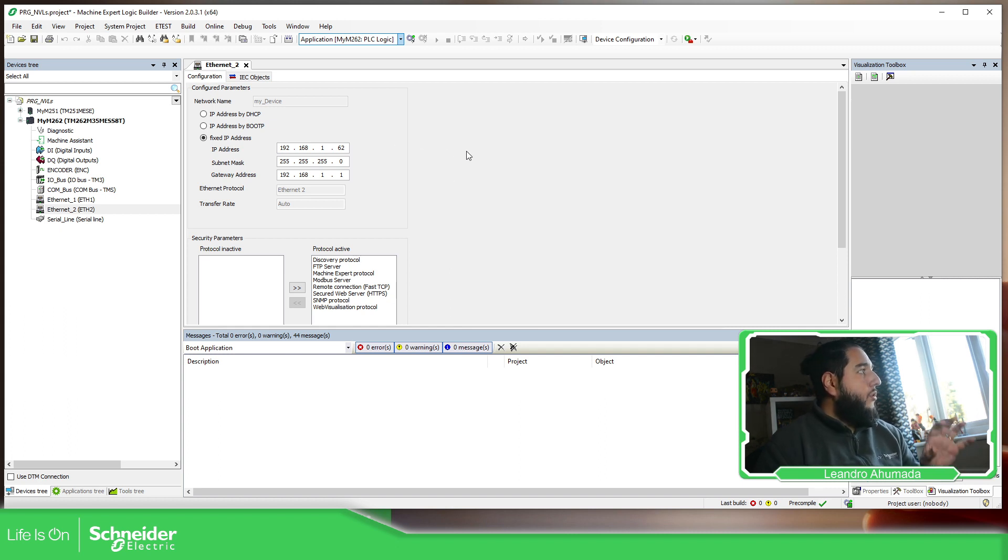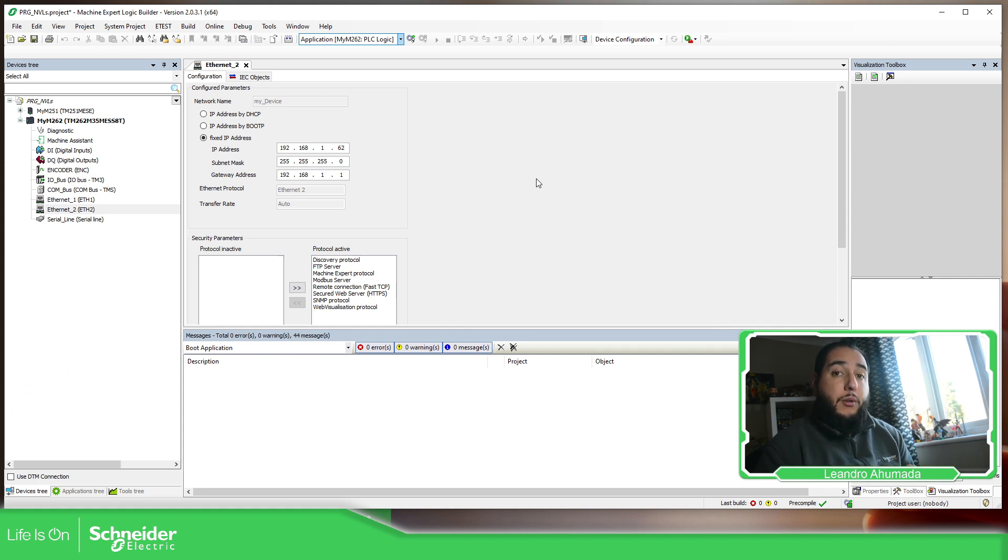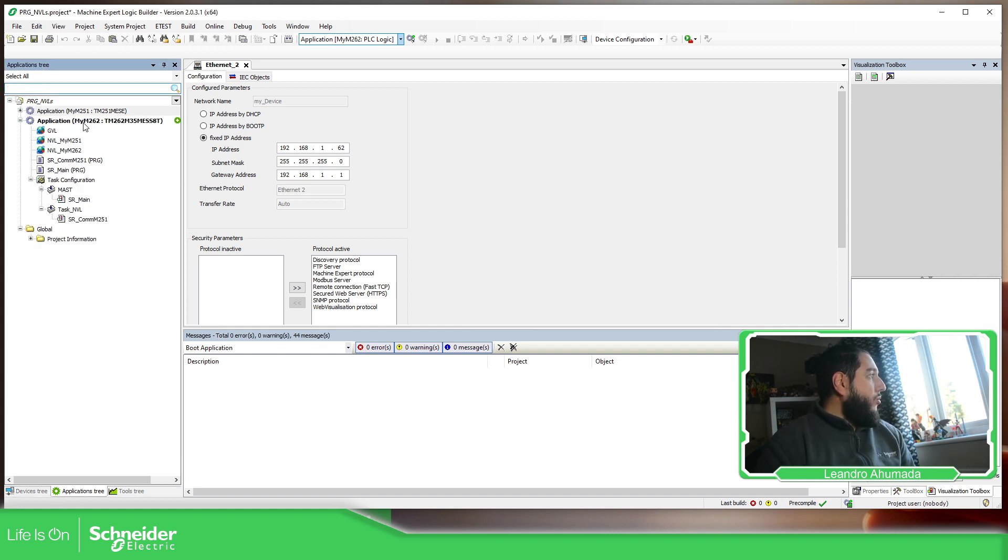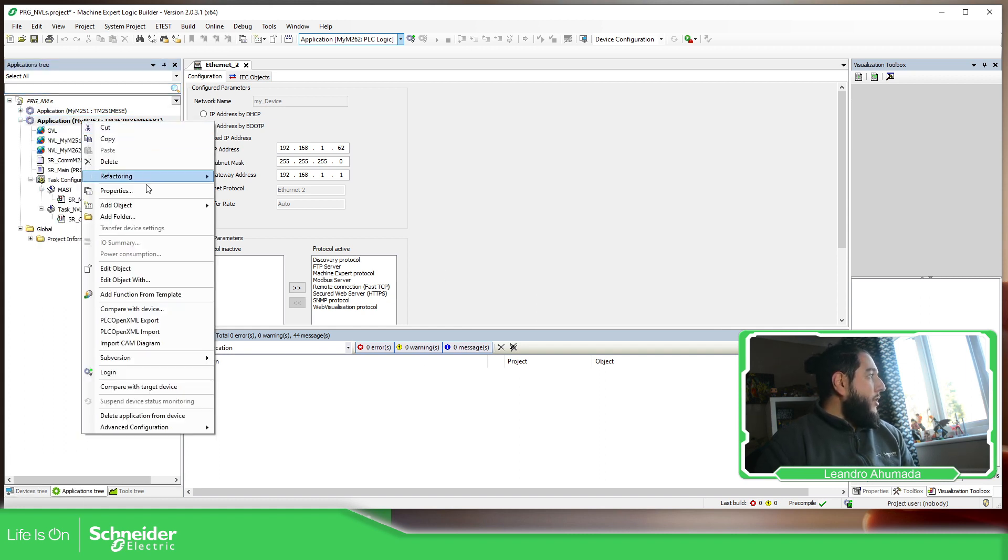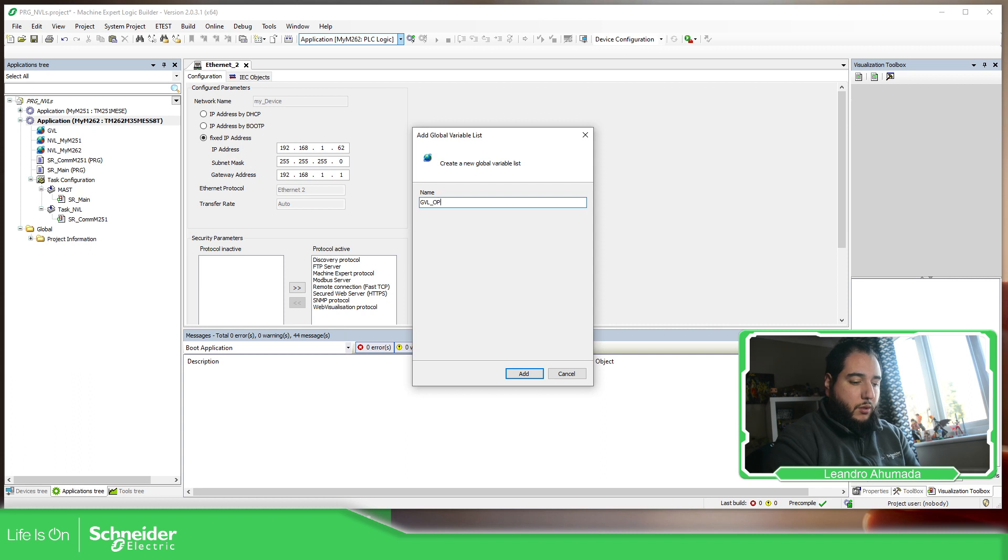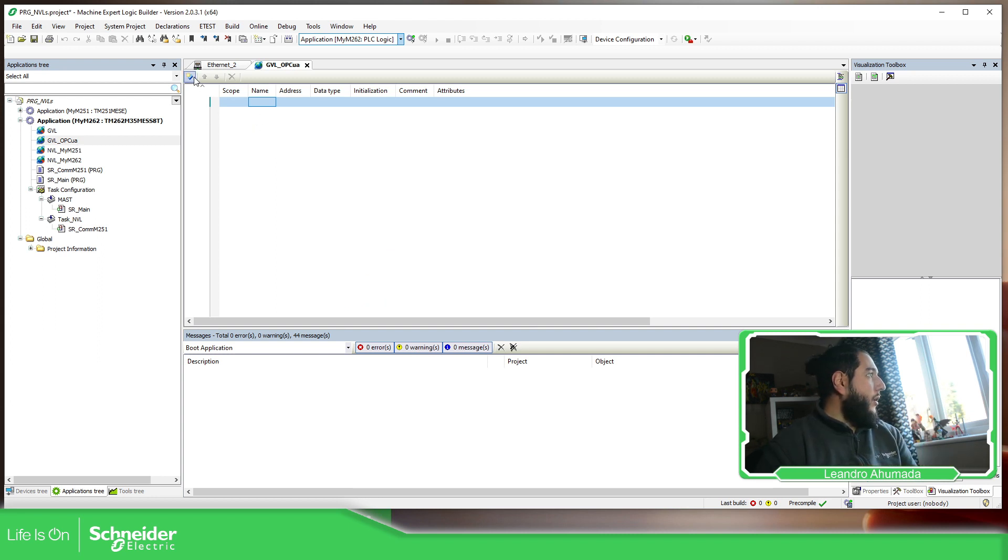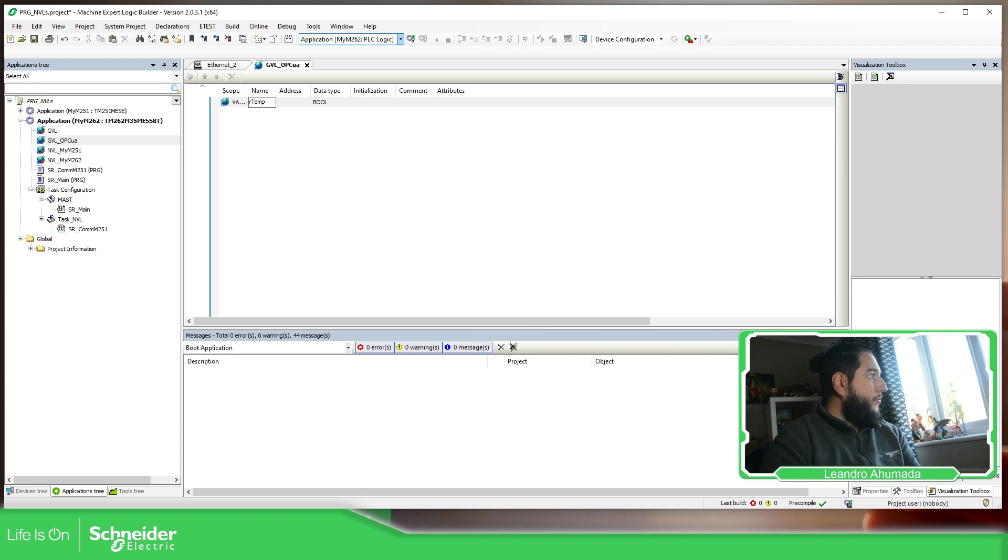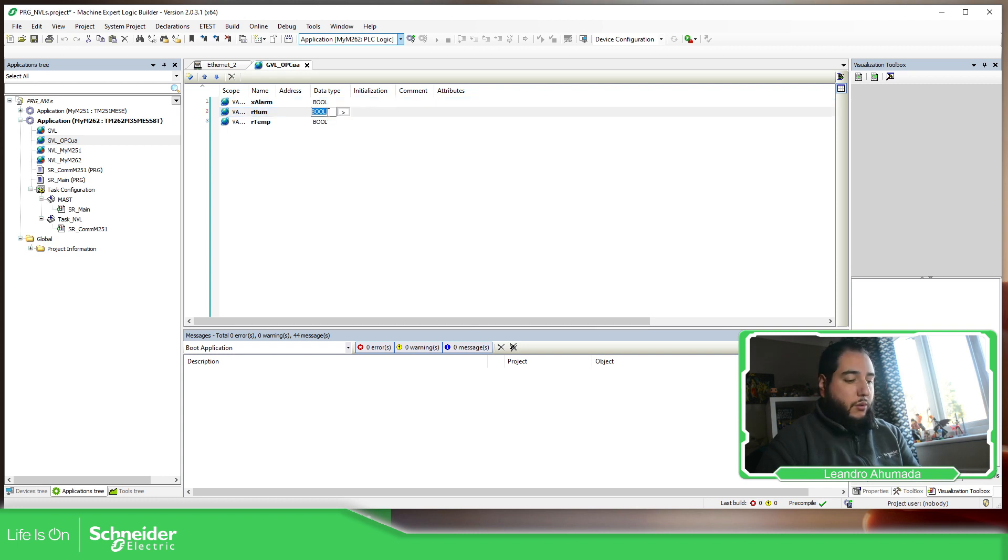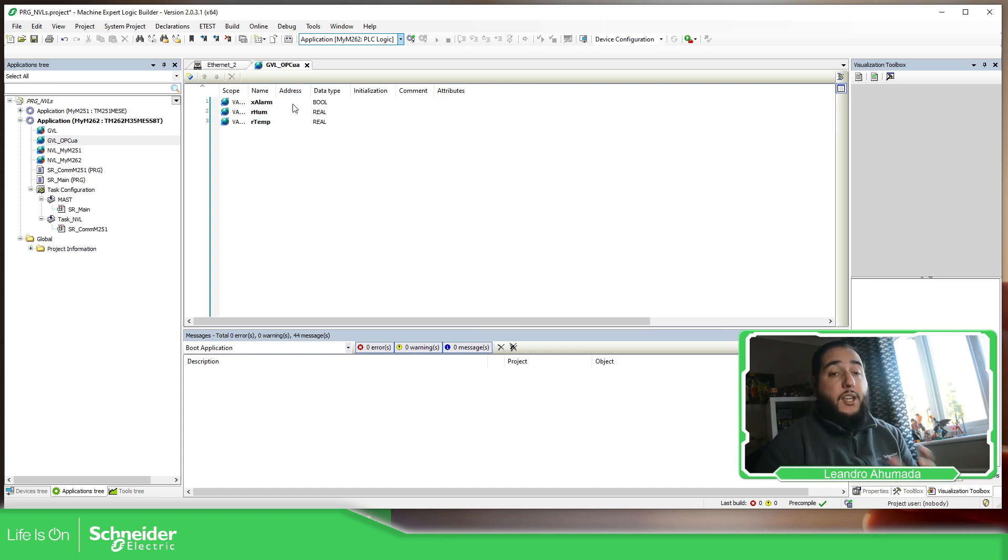As soon as you configure the settings of the Ethernet port, what we need to do is define which variables we want to share over the OPC. So we can create a new GVL object, GVL_OPC_UA. You can add different ones, but I'm going to create just one specific. So I'm going to use, for example, temperature, humidity, and I'm going to add xAlarm. These two are going to be real variables, this one real. You can see over here, I'm not going to specify any address because it's not needed for this.